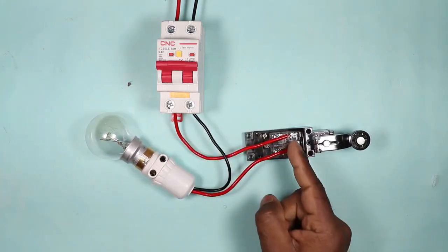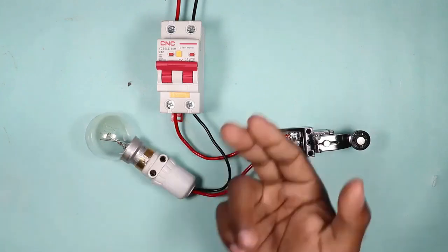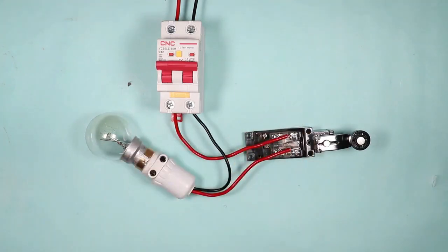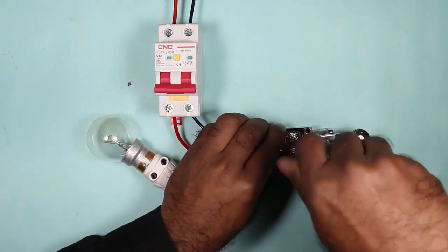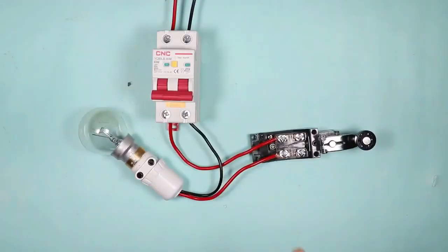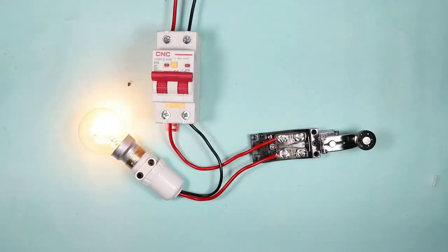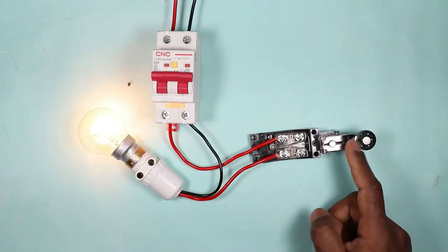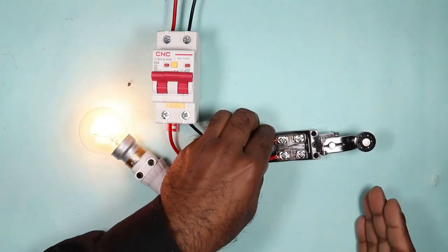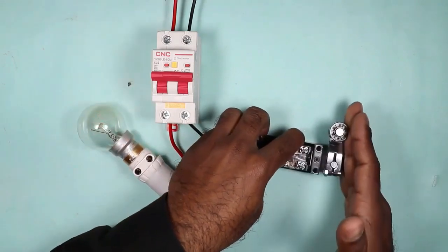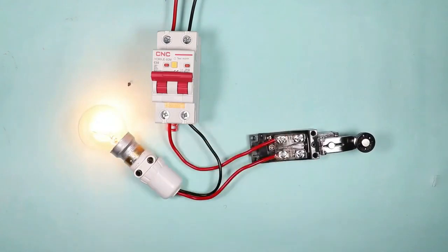On operating through NO contact, if the limit switch does not operate, then this lamp or signal will not be generated. Now if you use NC contact of the limit switch, let's change the connection fast. So now I connected the wires at NC contact. When I turn on this MCB, you can see the lamp is in on condition. This means the output command is generated by the limit switch. When an object touches the switch in this way and there is a movement in the plunger, then the lamp will turn off. On releasing the plunger, the lamp will again turn on.